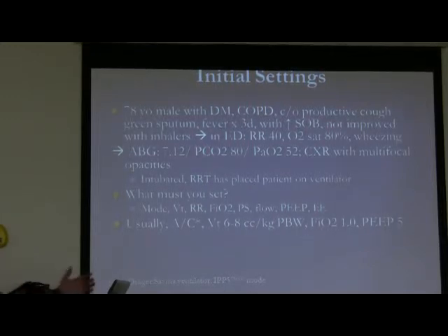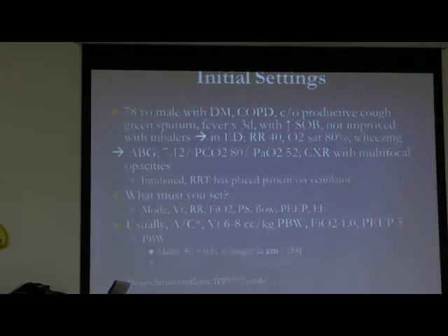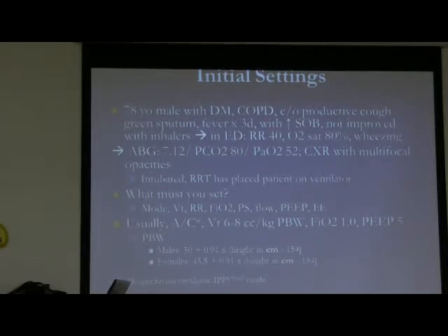Think of your short, fat person versus the tall, thin one in terms of what the lung capacity will be. FiO2 will be 1 or 100% basically, because again, you want full control. And PEEP is just arbitrarily set at 5 unless there's another indication to do so. Once you've set the mode, then that'll determine what these other parameters are, including respiratory rate, FiO2, pressure support, flow, PEEP, whatever that is, depending on what the mode is. Okay? Predicted body weight here, I note, is based on height.